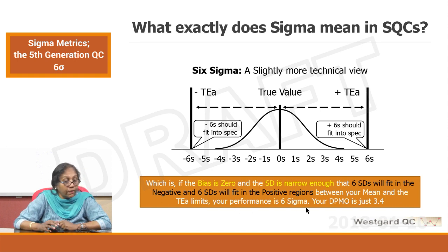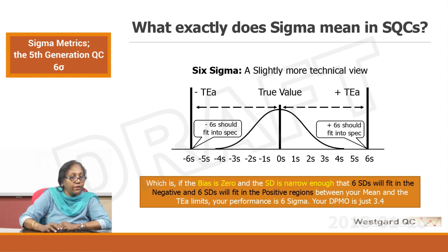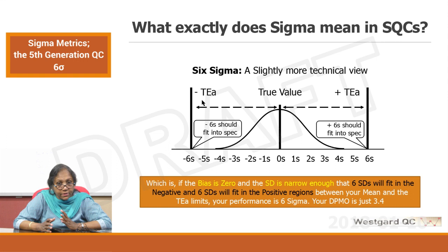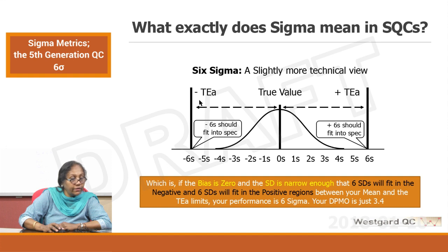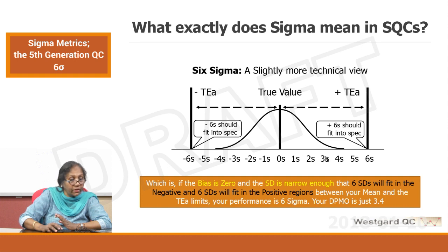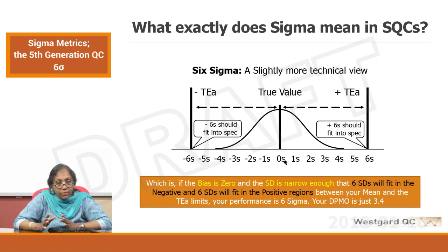When the bias is 0 and the SD is narrow enough that 6 standard deviations fit in the negative and 6 standard deviations fit in the positive regions between your mean and the total allowable error limits, your performance is 6 sigma and your DPMO is just 3.4. Total allowable error has lower and higher limits. Your Gaussian is standing right in the middle, your mean is the true value — there is no bias, your imprecision is very little — and you can accommodate 6 standard deviations on either side. This is your 6 sigma performance.